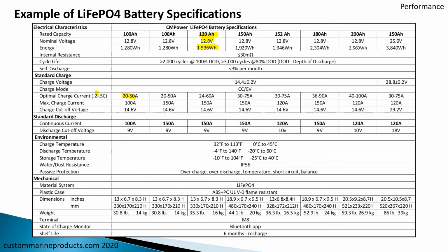The continuous current is how much current you can draw from these continuously and still keep your number of charge cycles high. Now, many batteries are typically 80 to 100 amp continuous discharge. We put 120 to 150 amp continuous discharge in most of our batteries, and you can look at it as making them heavy duty. So if I'm running my windlass and something else, and I need to start my engine with these batteries in a hurry, I need to be able to pull out a lot of power. And so for marine use, we think 120 to 150 amp max discharge is really important. Also, we have our temperatures that we can operate under and battery sizes. So these are the kinds of things that you see in battery specifications.